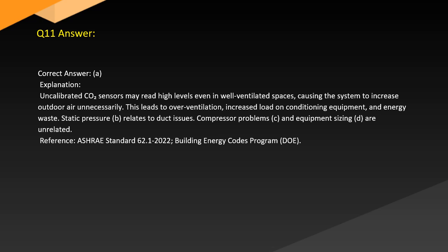Answer. Correct answer, A. Explanation. Uncalibrated CO2 sensors may read high levels even in well-ventilated spaces, causing the system to increase outdoor air unnecessarily. This leads to overventilation, increased load on conditioning equipment, and energy waste. Static pressure, B, relates to duct issues. Compressor problems, C, and equipment sizing, D, are unrelated. Reference ASHRAE Standard 62.1-2022, building codes.